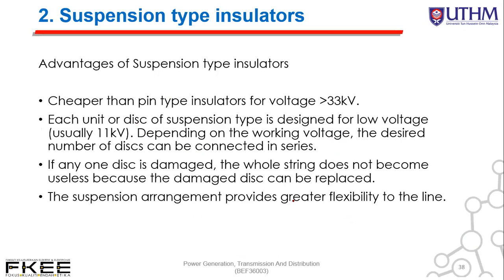Advantage of suspension type insulator. Yang pertama dia murah compared to pin type insulator, for voltage over 33 kV. Second, each unit or disc of suspension type is designed for low voltage, usually 11 kV. Kita dah bincang sebelum ni. Depending on the working voltage, the desired number of discs can be connected in series. If only one disc is damaged, the whole string does not become useless because the damaged disc can be replaced. Sebab dia stack of disc, so kita boleh tukar mana disc yang rosak. The suspension arrangement provides greater flexibility to the line.